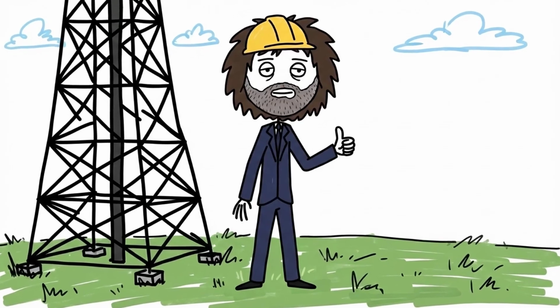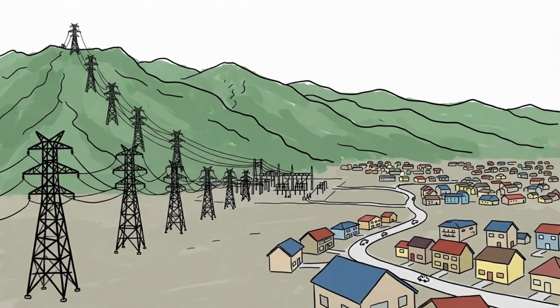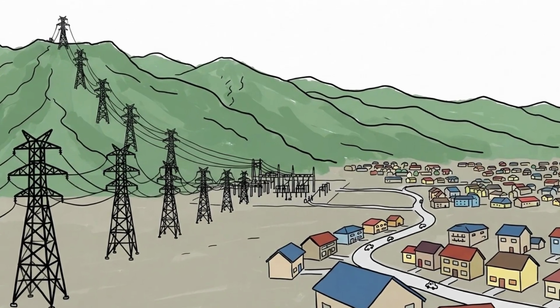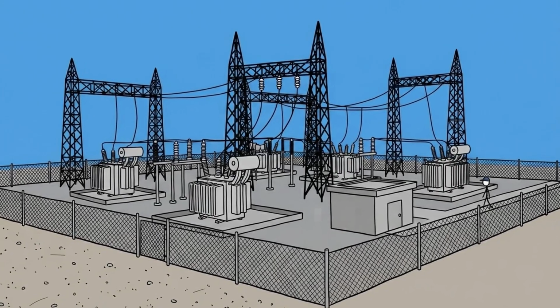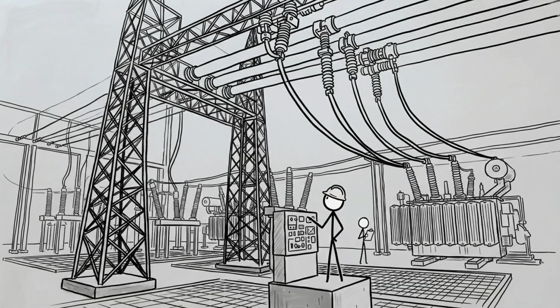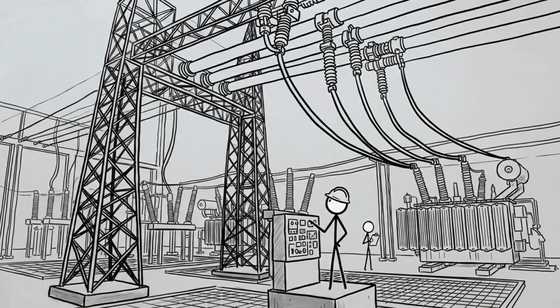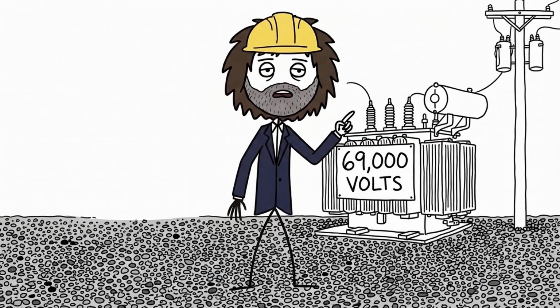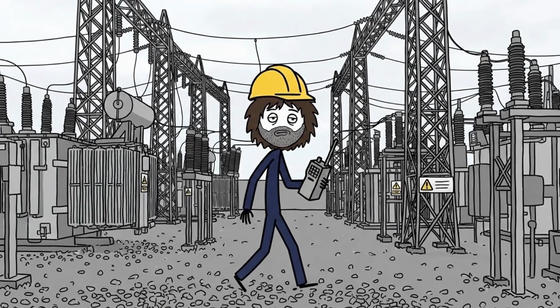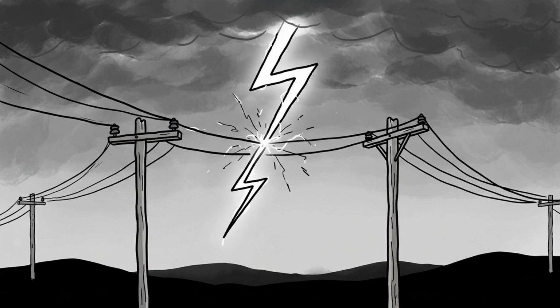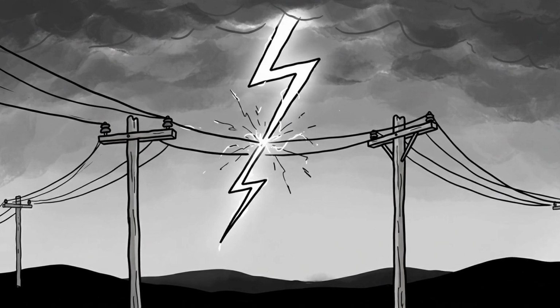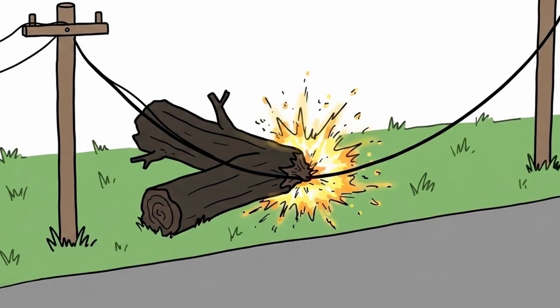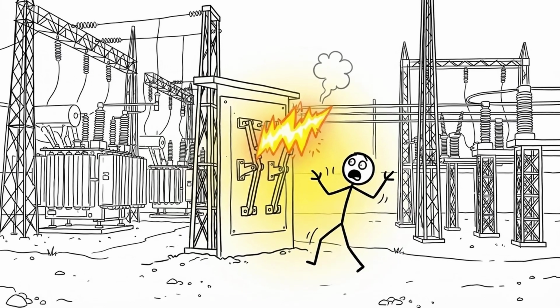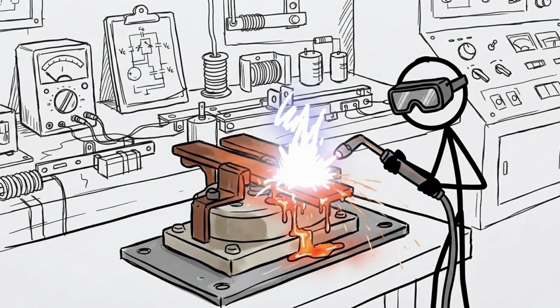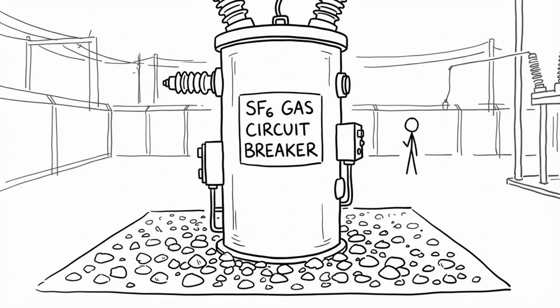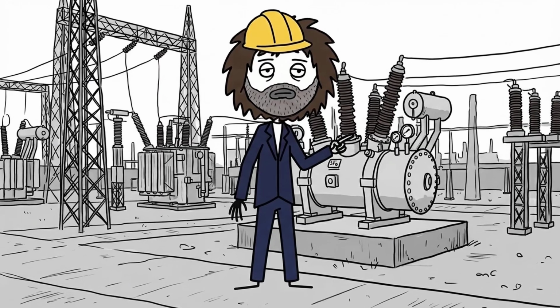As this high-voltage highway approaches your metropolitan area, the electrical pressure is far too dangerous to enter residential neighborhoods, so it makes its first major deceleration at a bulk transmission substation. Here, giant step-down transformers drop the voltage from hundreds of thousands of volts down to sub-transmission levels, usually around 69,000 to 138,000 volts. But managing this much raw power introduces a massive hazard. If lightning strikes a line or a transmission tower collapses, you cannot simply open a standard mechanical switch to cut the power, because pulling high-voltage electrical contacts apart creates a blinding plasma arc hotter than the surface of the sun that will burn straight through solid steel.